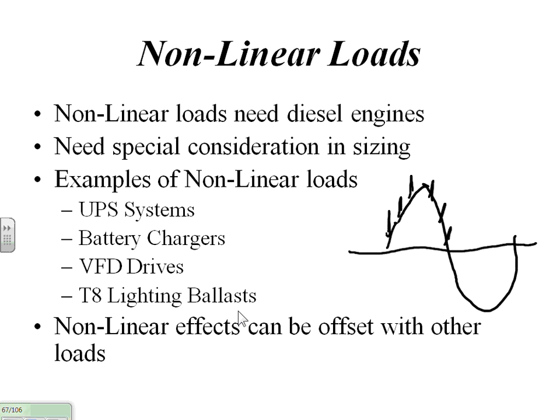Well, now we'll put the notches back in. And natural gas sets, for whatever reason, if they're shunt excited, that gets coupled back to that regulator, and it sees these notches as zero crossings, and the thing just goes nuts. This problem has been pretty much fixed in the industry over time, and it was primarily due to the SCRs when UPSs came up.